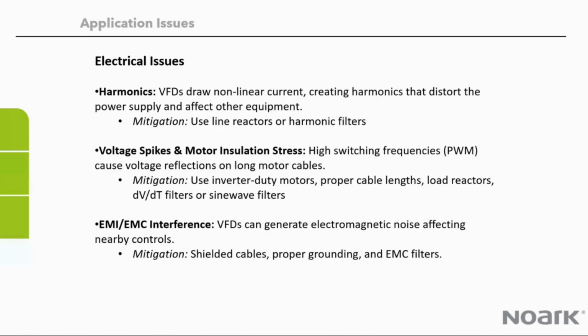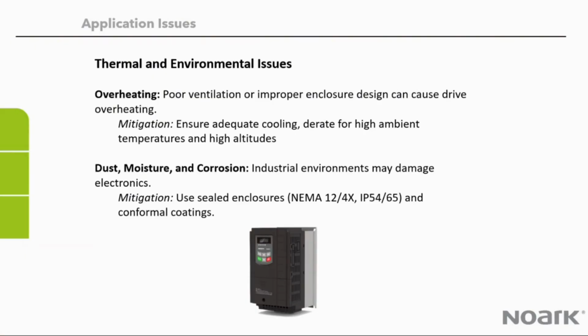Voltage spikes and motor insulation stress: drives generate high switching frequencies, and on long cable lengths can cause voltage reflections. The recommendation is to use inverter duty motors, move the drive closer to the motor itself, use load reactors, dV/dt filters, or sine wave filters. VFDs can also generate electromagnetic interference and affect your other automation systems or process control systems. Shielded cable, grounding, and filters would help you overcome that.